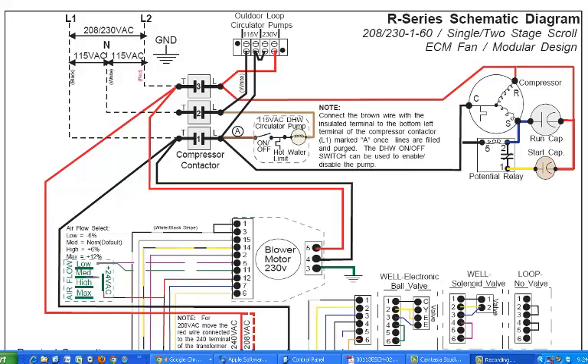With respect to that, we are going to take a look at the system, as I mentioned, in a series of videos, broken down component by component, or at least section by section, to understand what goes on with it. We're going to start with this introductory video with the high voltage side, just because that's where the power is initially introduced into the system. Ultimately, where we're looking to go is understanding all that happens within the electrical portion of the heat pump, because not only is that an area where it's critical that you understand it, but also the electrical system has diagnostics available within it that will help you trace down other problems that might be showing up.